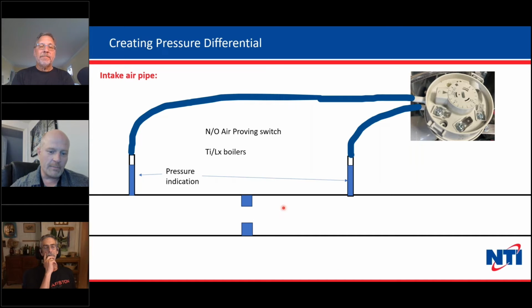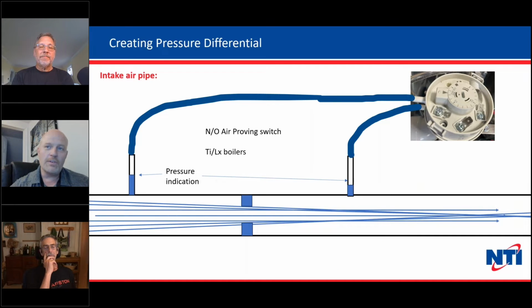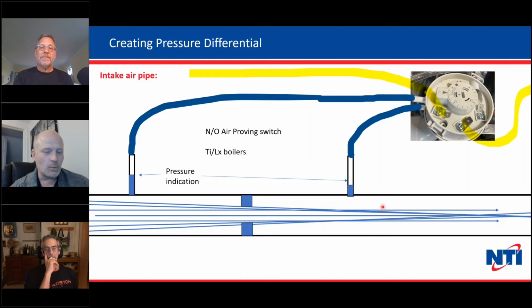And if I can get my slide to work for me. There we go. So we've got our air coming through. After we pass through the restriction, you can see that on the right-hand side, we've dropped and lost a lot more pressure than we did on the left-hand side. And that's because this restriction creates a drop in pressure. Now, the reason we do this is if we only used a single tube, it just tells us that there was a pressure drop and it doesn't tell us whether there was flow. By using two pressure tappings in the same pipe and creating an artificial restriction in the middle, it allows us to characterize the airflow through that intake pipe or exhaust pipe, as the case may be.